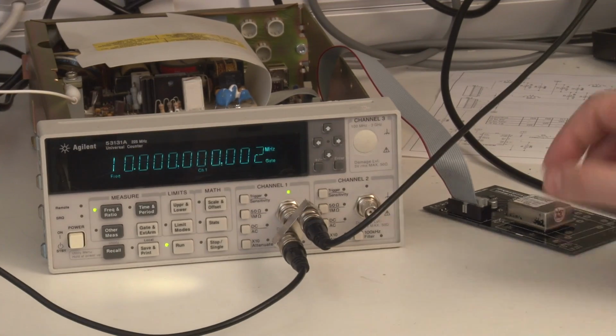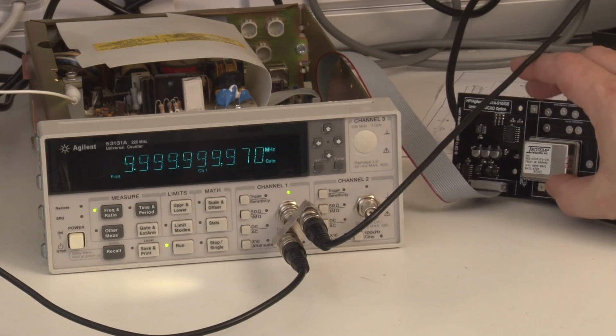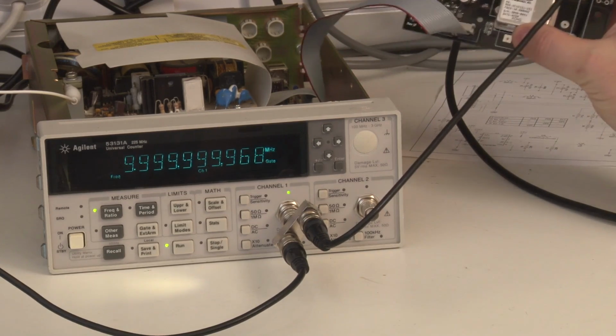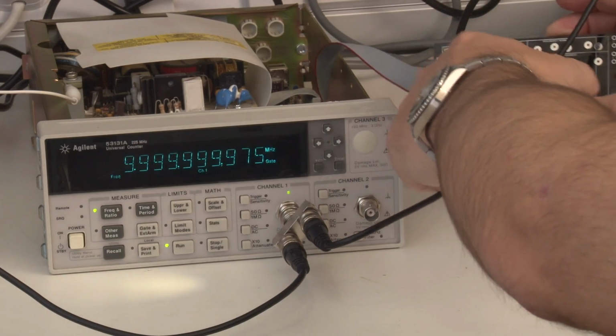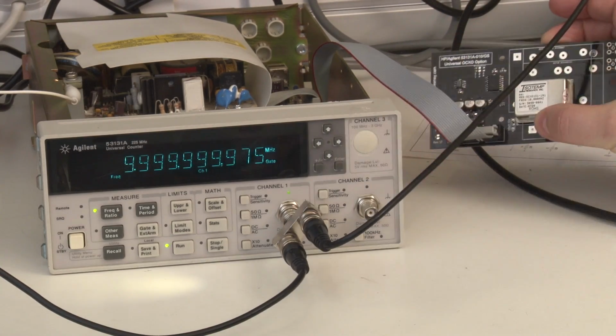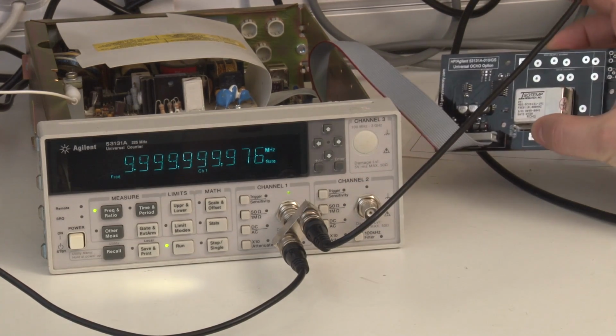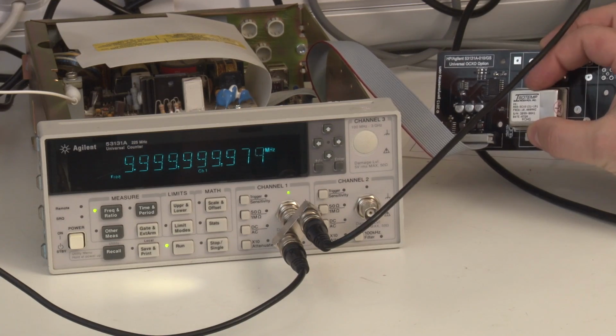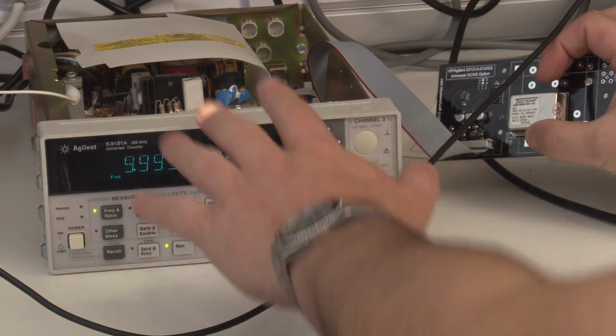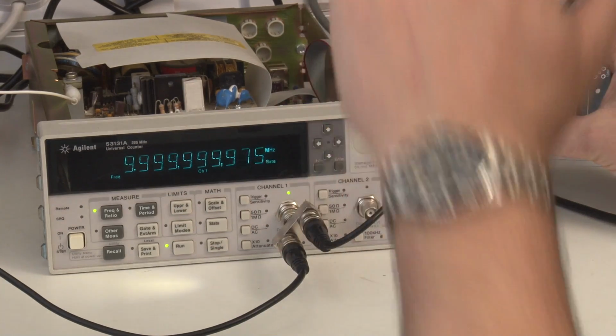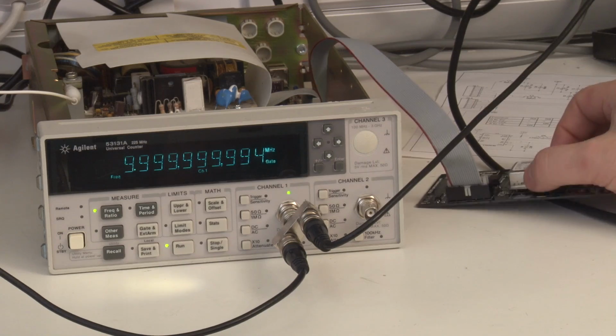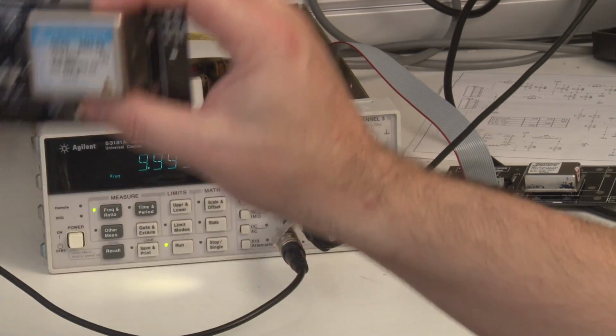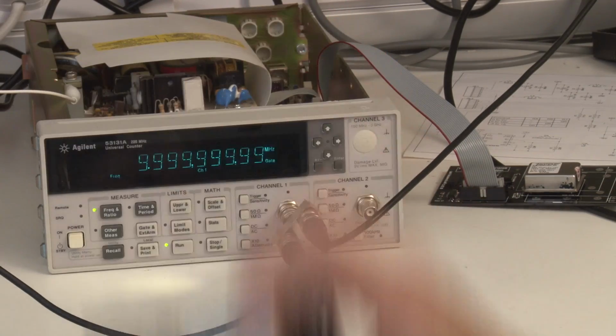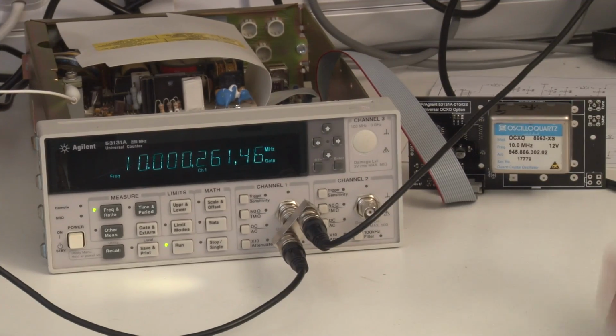Okay, this one failed its calibration. I had to mess around with it a little bit, and in the end I had to use a different mode, the plus or minus 5 volt mode. Not that it sits at a negative voltage at all, it actually sits at about 2 volts, but for some reason the firmware in here doesn't calibrate it properly. But if I moved it to there, I'm going to do the oscilloquartz ones. Okay, so there it is working.